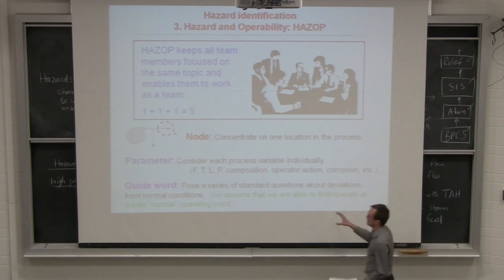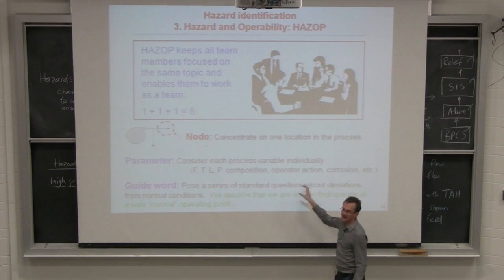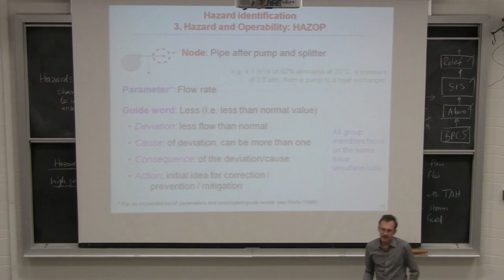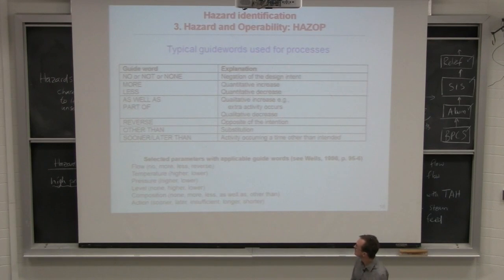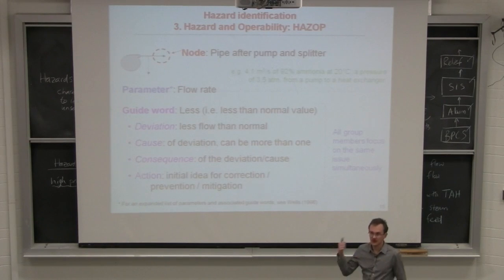So you can see how combinatorial this is and why this is more than a few hours to even HAZOP a simple process. And once you've picked up your parameter, then you're going to pose some guide words that are relevant to that parameter. So you're going to look at deviations. Your guide words can be of several types. If we consider the node to be the pipe after the pump and after the splitter, the parameter we might consider is flow rate. So we've got our node, we've got our parameter, and the guide word I might select is less.